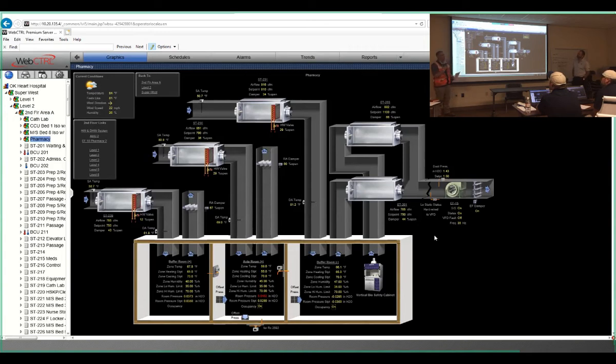So what we ended up doing is we prioritized the air on the second floor manually through the return system. We first dumped all of the air back into the pharmacy. It comes down and splits, feeds the pharmacy and the cath lab, and then goes over and feeds the rest of the floor. So we manually manipulated those dampers to prioritize that first, so this gets satisfied before the rest of the space. You guys should know that, because if you have issues on one side or the other, you've got to know what we did and how we set it up to make it work.